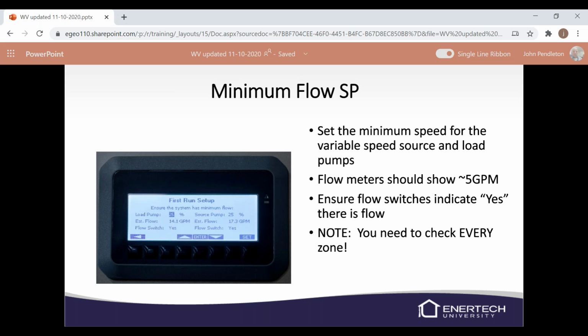And you can see how the 25 here on the load pump is highlighted. Once it's highlighted, you can press enter and move it up or down on your percentages. And you can look at your GPM and see what your flow is. This is where you can also set up your bypass valve if you've got a bypass valve set up in it, so we can make sure we've got proper water flow through there. Do it on the load and the source. And make sure that whatever the pump minimum is, where it says estimated flow, you have at least 5, and that it says flow switch yes.